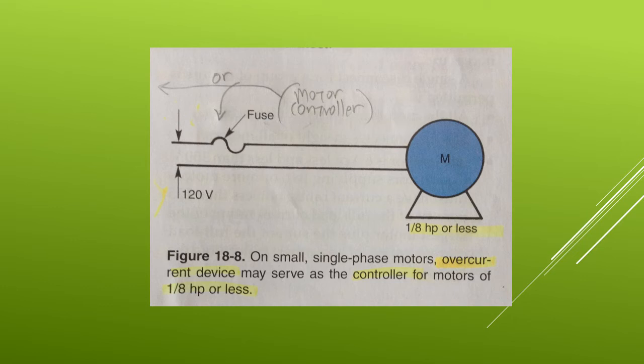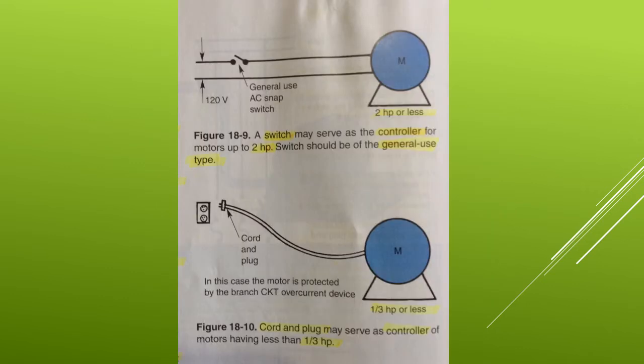For motors up to and including 2 horsepower, the controller may be a switch. This switch should be of the general use type and have a current capacity of at least twice the full load current rating of the motor. The switch may also serve as a disconnect. For this, see figure 18-9, top of the screen, which shows a suitable switch.